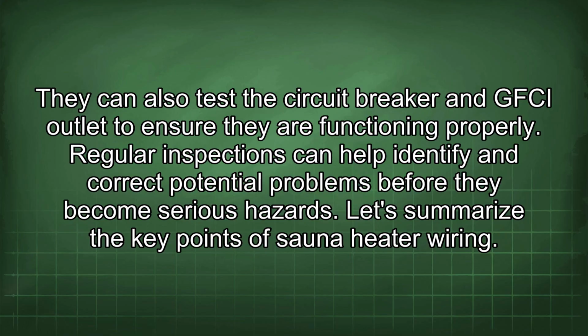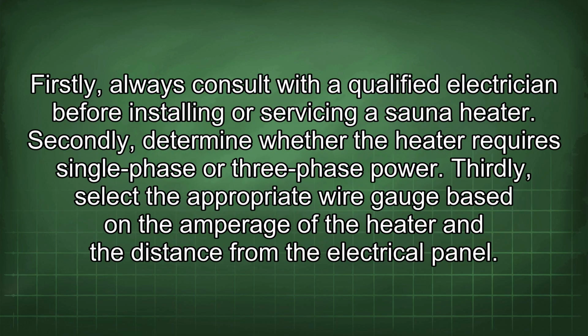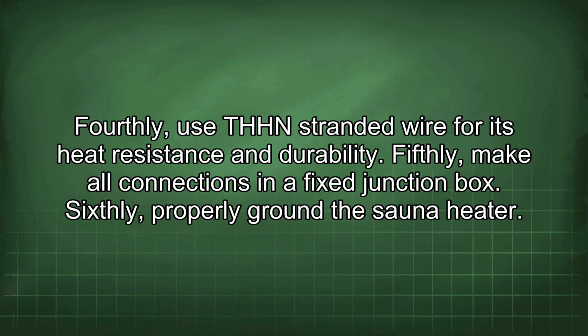Let's summarize the key points of sauna heater wiring. Firstly, always consult with a qualified electrician before installing or servicing a sauna heater. Secondly, determine whether the heater requires single-phase or 3-phase power. Thirdly, select the appropriate wire gauge based on the amperage of the heater and the distance from the electrical panel. Fourthly, use THHN stranded wire for its heat resistance and durability. Fifthly, make all connections in a fixed junction box. Sixthly, properly ground the sauna heater.